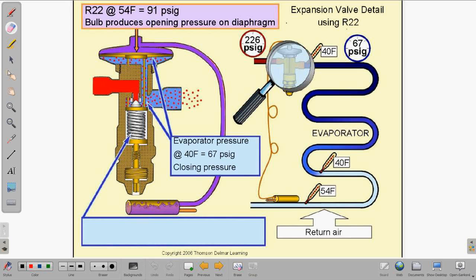So here's our evaporator pressure right here, and it flows through the valve and pushes upward on the diaphragm from the bottom side of the diaphragm. The evaporator pressure is 67 psig. Now, if you have your gauges on there, 67 psig and 40 degrees Fahrenheit of the refrigerant, if you cross that over on your pressure temperature chart, that is 67 psig. So now we have 91 psig pushing down from the bulb temperature, which is 54, and we have 67 psig pushing up on the bottom of the diaphragm.